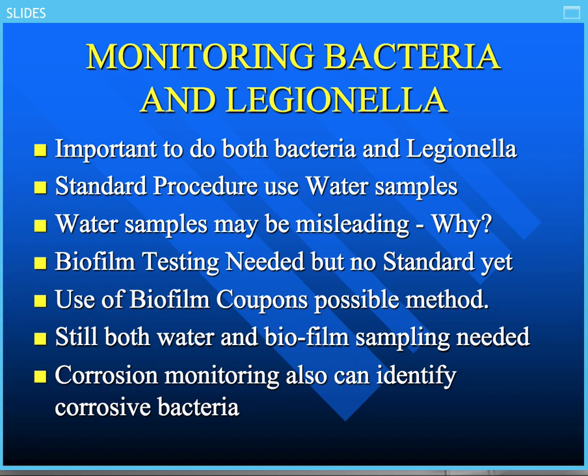But the problem is we don't really have a standard developed as yet for a technique to take a certain amount of biomass and then use that. Now, we've developed what we call a biofilm coupon, and that's a possible method to use. It's similar to a corrosion coupon, 1/2 inch by 3 inches, but it's made out of stainless steel wire mesh, and that mesh acts as a place for the biofilm to be trapped and grow. We utilize that biofilm coupon to capture the biofilm, and then we knock off that biofilm in some sterile water and test the biofilm for total bacteria. Then we're coming up with what is present in your system.